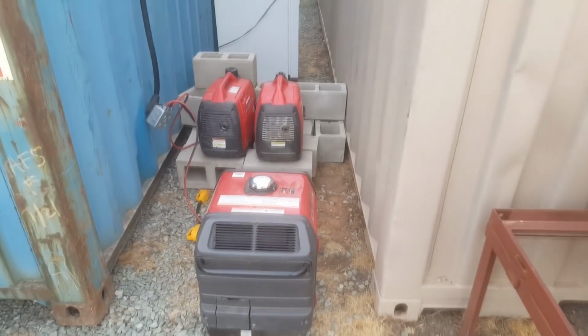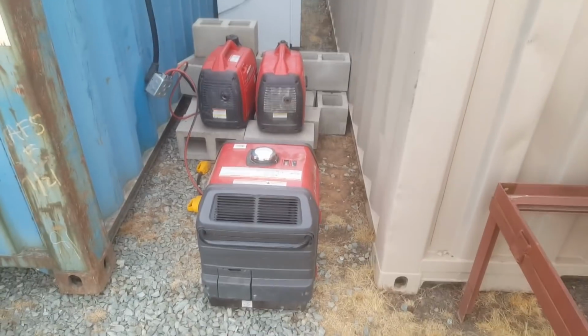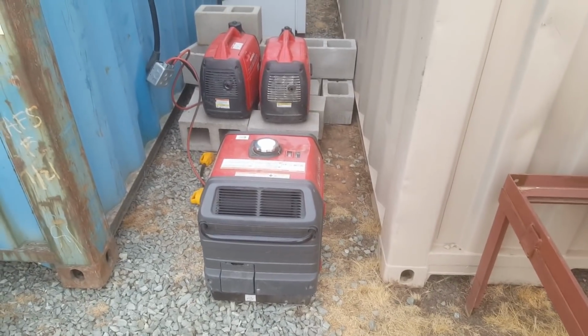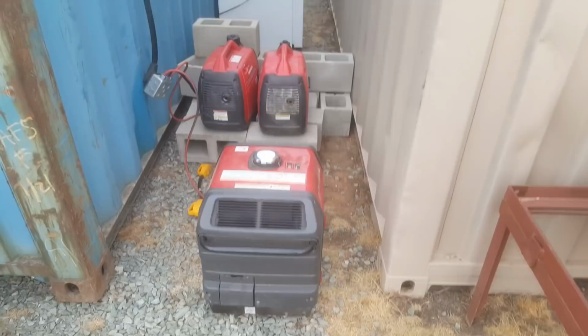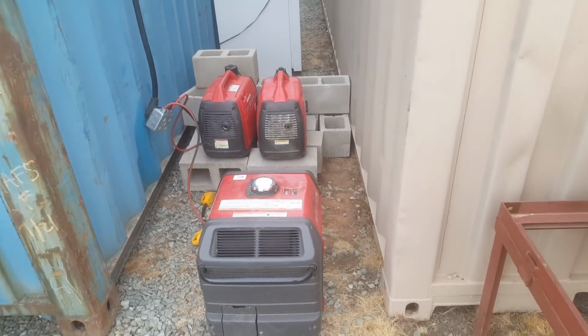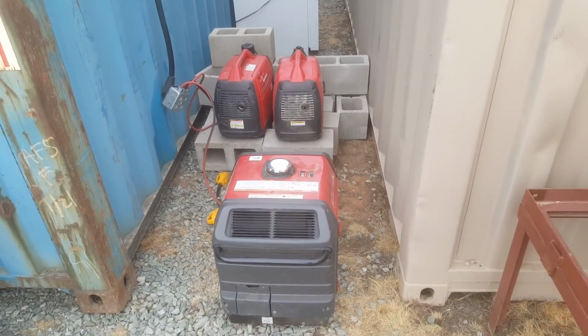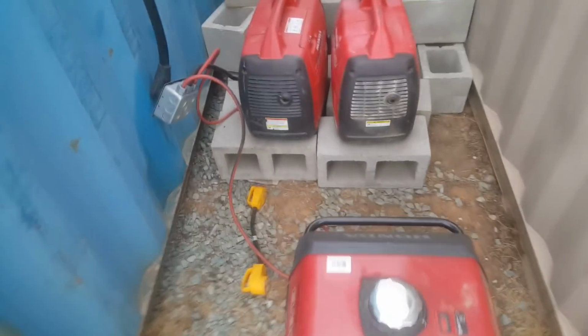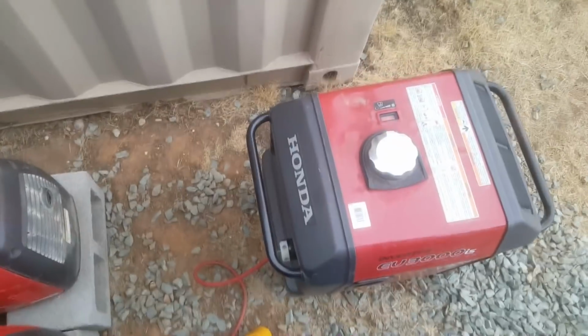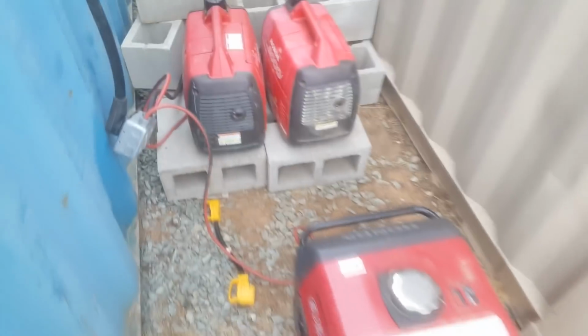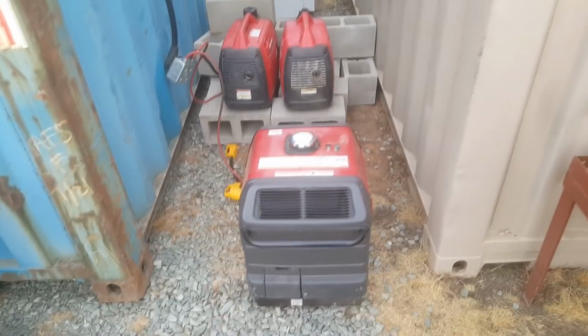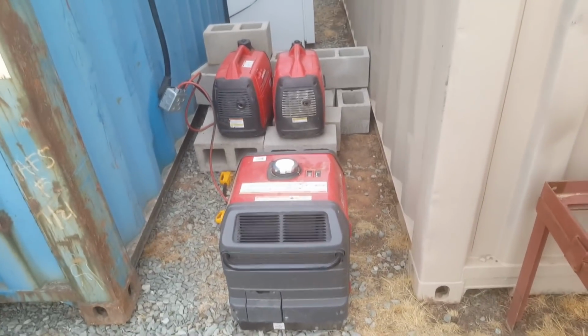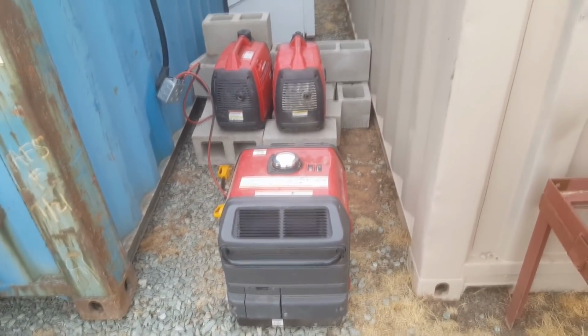I'm going to start these up so you can tell what they sound like. These are the generators about 5 feet away at close to full load, but it's not full load because the sun is still out some and the solar panels are still making power. So they're a little noisy. Even though they're supposed to be really quiet, but for what they do and their fuel consumption, I can't complain. They work really well. It sounds like they slowed down a little bit, almost like the batteries are near full.